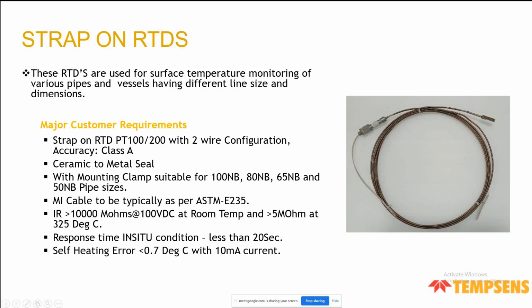Then different mountings are there according to the pipe size. The mineral insulated cable has to be as per ASTM E235, which is for critical environments. So it requires special testing of the cable, and special purity of the MgO. Then the size of the conductor is also different. There are also a lot of tests on the outer sheath, and the cable for this RTD has to be made according to this standard. The insulation resistance required by the customer is greater than 10,000 megaohm at room temperature, and at high temperature more than 5 megaohm. And there must be a very small self-heating error.